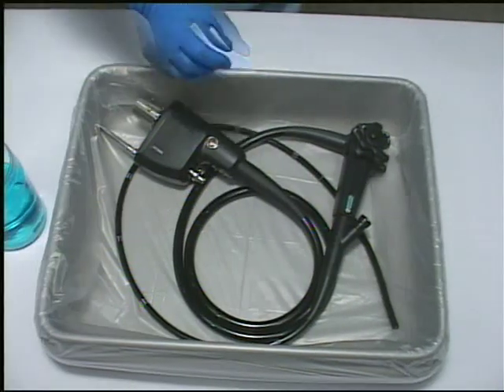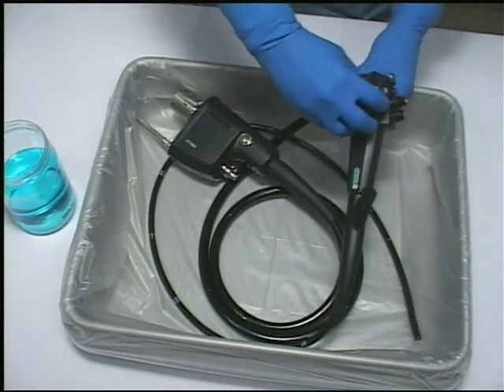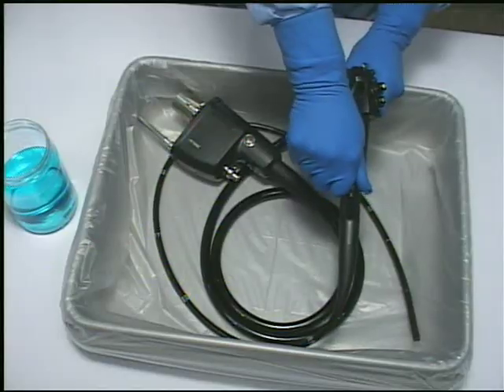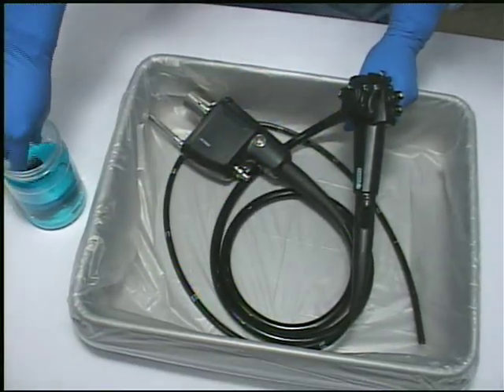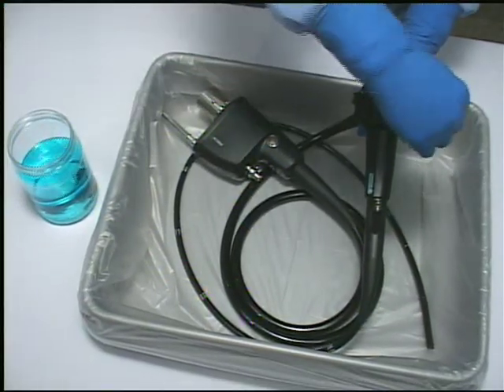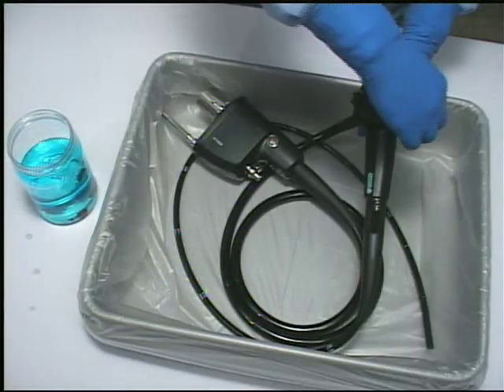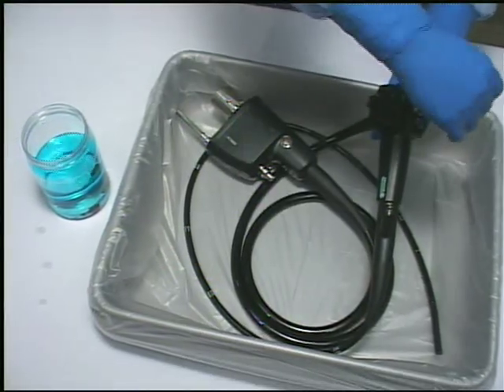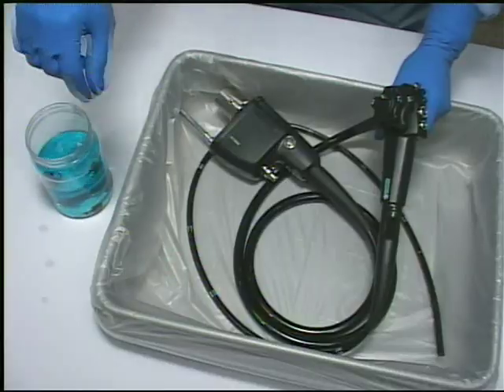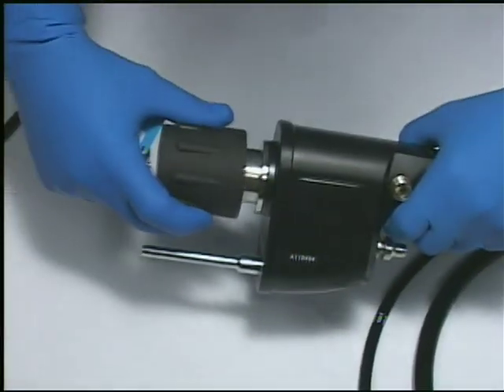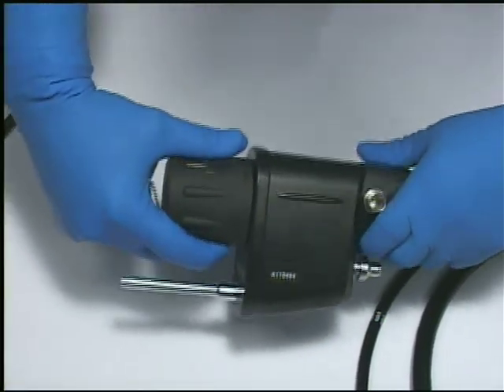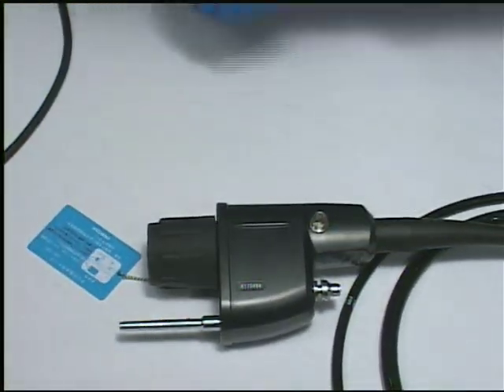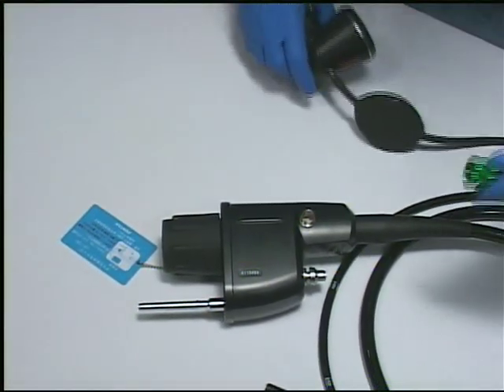Stage 1. Dry test. All valves, inlet seals, and other removable components should be detached from the scope prior to leak testing. The dry leakage test should be performed prior to immersing Pentax endoscopes in any fluid. This test detects any major loss of integrity in the endoscope's watertight construction, for example, a major tear in the instrument channel.